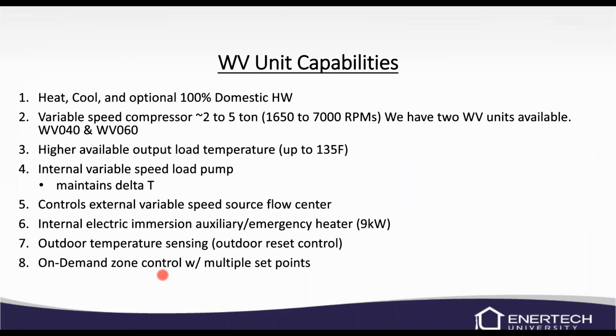So we'll go ahead and dive into the variable speed water to water unit. We'll call it the WV unit. W stands for water to water, V stands for variable speed. Basically this unit will do heating, cooling, and up to 100% of your domestic needs. Now I say up to, the TurboMax tank is able to handle a standard hot water flow through a shower head or maybe a washing machine.